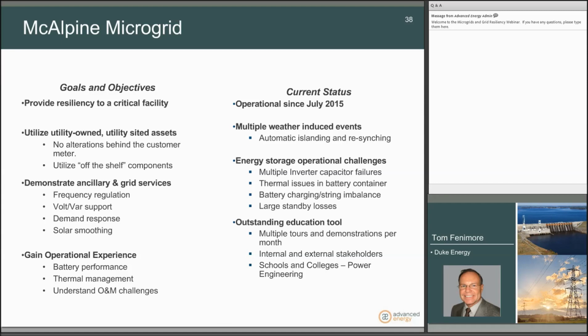In addition to providing backup energy to the fire station, we wanted to demonstrate ancillary and grid services—what are the values of microgrids when they're not actually backing up the customer? In this case, that meant frequency regulation, solar smoothing, potential demand response, and volt-var support for the grid. All of these have been tested at McAlpine and made operational as part of the microgrid.